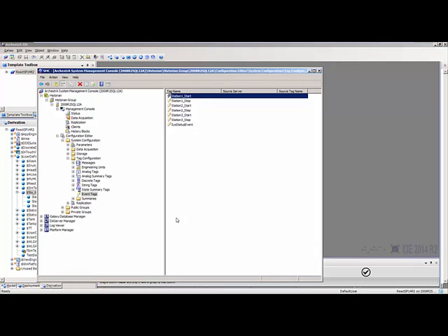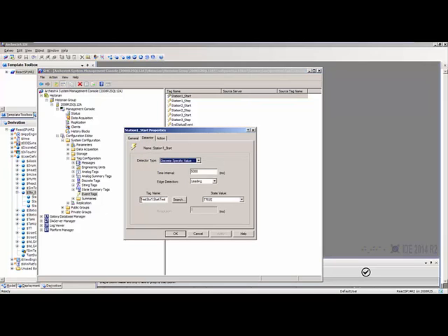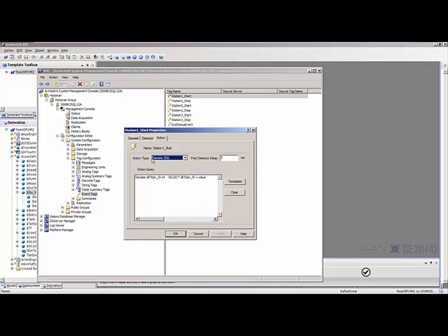Let's take a look inside the configuration of the Wonderware Historian. We're using something called an event tag inside the historian to log that information to the table we just looked at. An event tag has a detector — here it's detecting the startup test bit — and then it takes an action. In this case the action is going to execute a SQL command that does a select, getting that ID from the live table in the system and getting the live tag name where the Titan ID is.